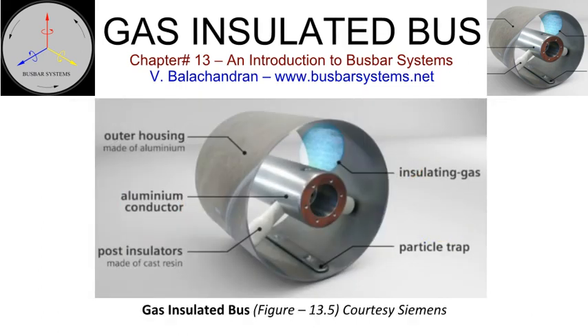The main components of a GIB are enclosure, enclosure support, conductor, conductor support, insulator or bushing, insulating gas. In addition to these, there are several accessories, comprising telescopic finger contact assembly, compensators, isolating device, particle traps, terminations, lightning arresters, protection against corrosion, cathodic protection, for buried GIBs.